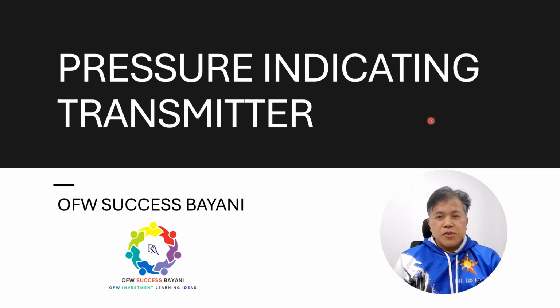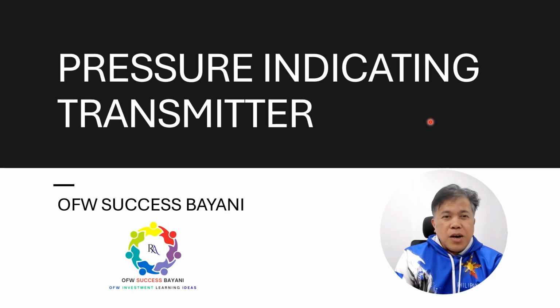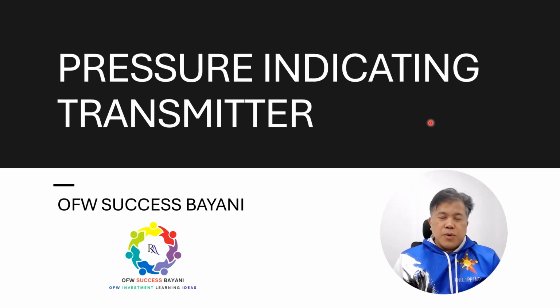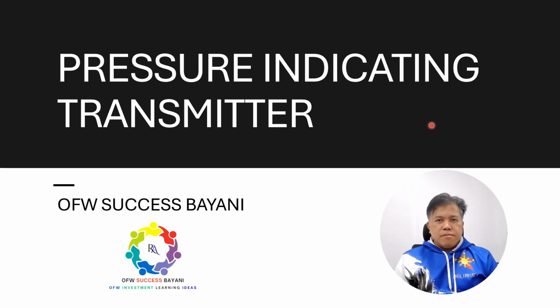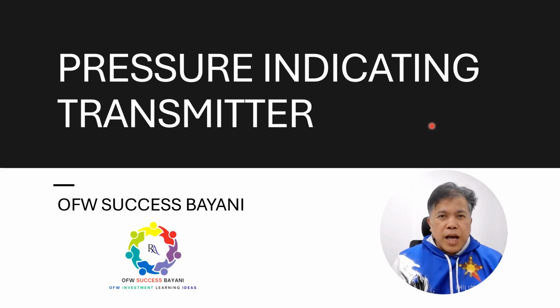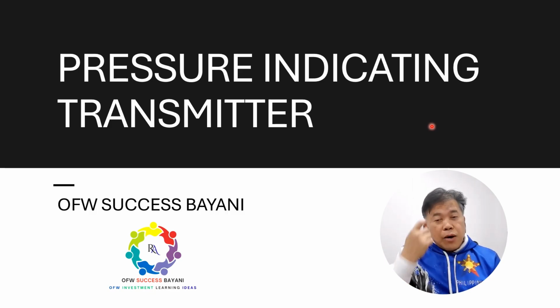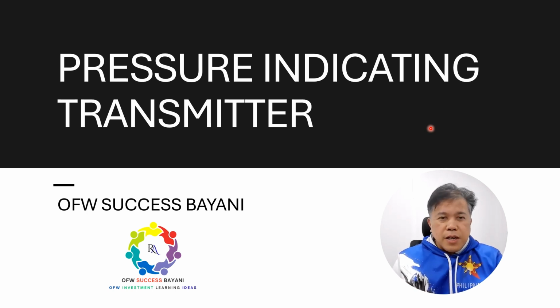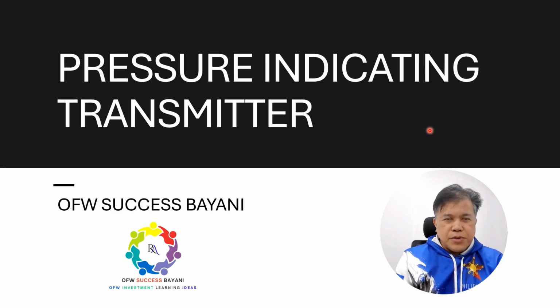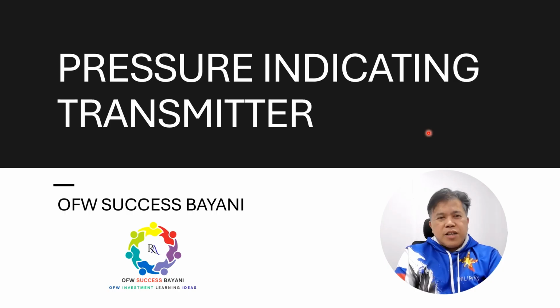So without further ado, we will start. Today we are discussing pressure indicating transmitter. We're talking about pressure transmitter. So the pressure transmitter is something that we have to inspect based on our checklist, and also what kind of testing we are doing as part of the activities during the site, and also the calibrations as well. So prior to the calibration, we do the installation, and then we proceed to calibration. So we'll start now.